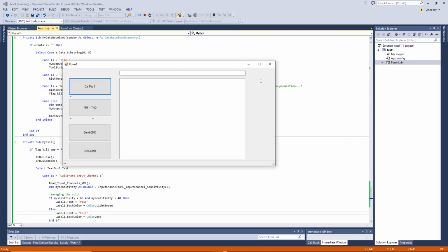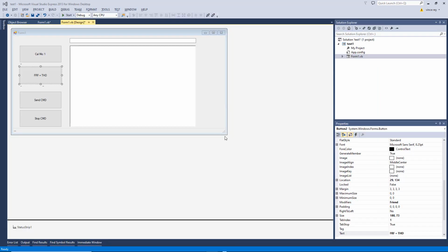I'm still calibrating the microphone. The calibrator is on, so I'm going to click cal here. And after the 5 seconds, I'll have a pass here, which is a good sign. So the sensitivity is equal to 53 millivolt per Pascal, and the label reference that and will tell me that the microphone is healthy.